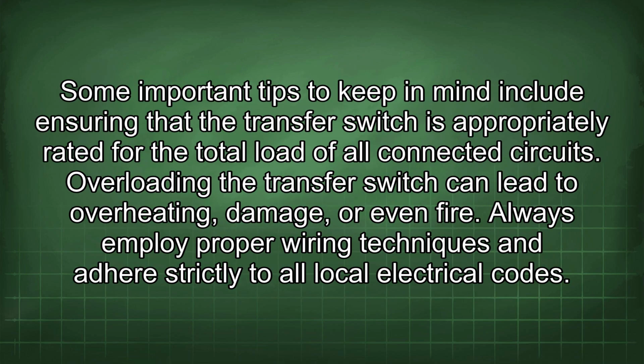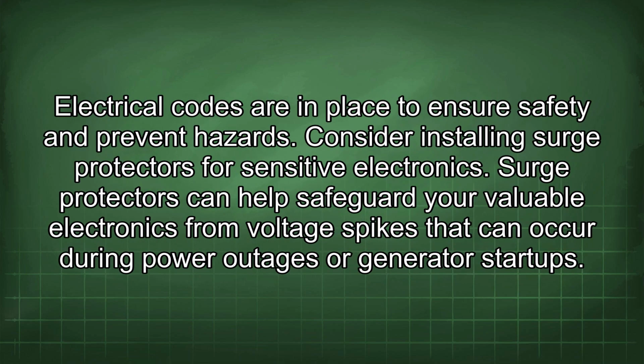Some important tips to keep in mind include ensuring that the transfer switch is appropriately rated for the total load of all connected circuits. Overloading the transfer switch can lead to overheating, damage, or even fire. Always employ proper wiring techniques and adhere strictly to all local electrical codes. Electrical codes are in place to ensure safety and prevent hazards.